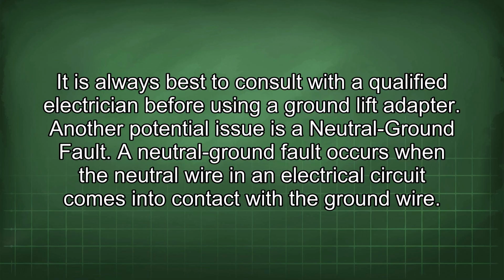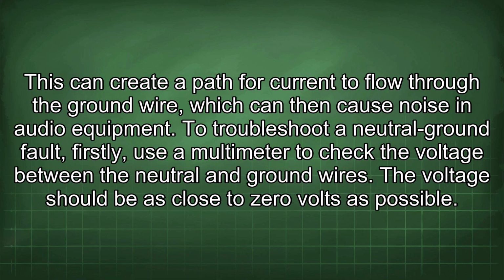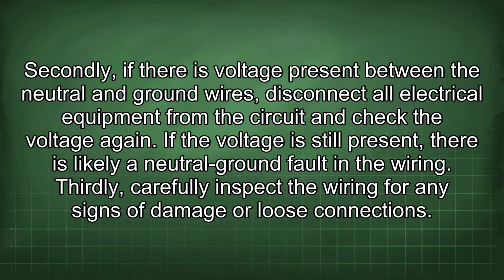Another potential issue is a neutral ground fault. A neutral ground fault occurs when the neutral wire in an electrical circuit comes into contact with the ground wire. This can create a path for current to flow through the ground wire, which can then cause noise in audio equipment. To troubleshoot a neutral ground fault, firstly, use a multimeter to check the voltage between the neutral and ground wires. The voltage should be as close to 0 volts as possible. Secondly, if there is voltage present between the neutral and ground wires, disconnect all electrical equipment from the circuit and check the voltage again. If the voltage is still present, there is likely a neutral ground fault in the wiring.